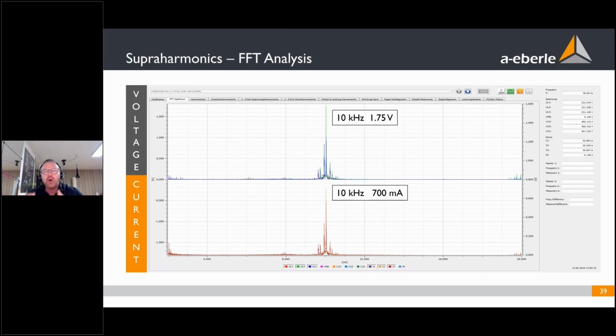If we analyze what disturbances this car produces for our network, we see on the current, if the car charged with 16 amps, we see 700 milliamps at 10 kilohertz. Over the impedance of the network, we see a voltage drop of 1.75 volts, also at 10 kilohertz. Be aware that at 50 hertz, your impedance is much smaller than at 10 kilohertz. At 10 kilohertz, in your normal low voltage grid, you calculate with an impedance of 5 ohm or sometimes 10 ohm. So a small current can produce a bigger voltage, and the voltage will be the problem for all other devices in this low voltage grid.